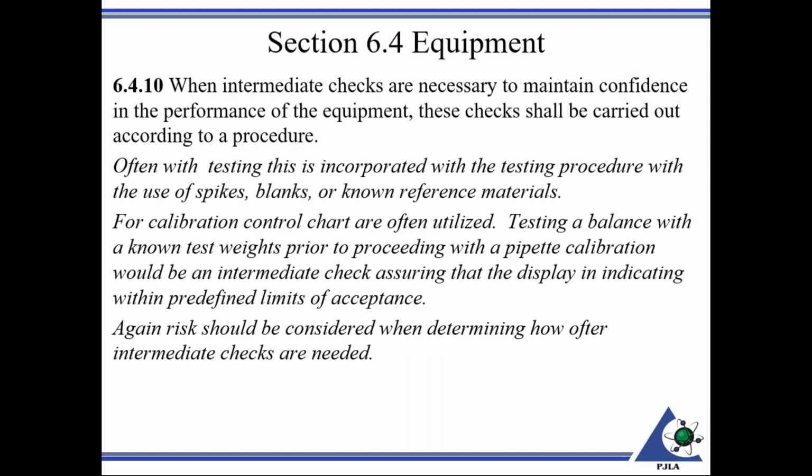So, intermediate checks. When intermediate checks are necessary to maintain confidence in the performance of equipment, these checks shall be carried out according to a procedure. So of course, when you send your equipment out, say for calibration, and let's say you have it on an annual basis, you have a warm fuzzy feeling when it came back. Hey, it's operating. It's been calibrated. It's within where we need to keep it. Where it needs to be.